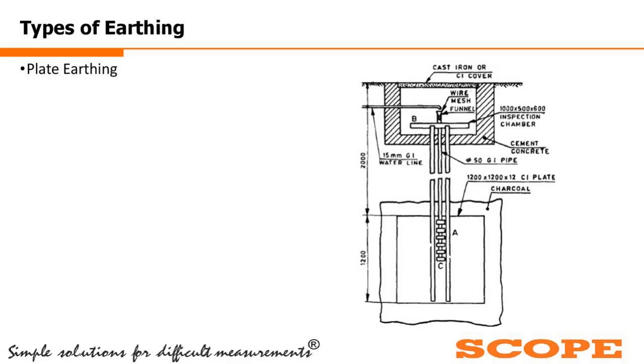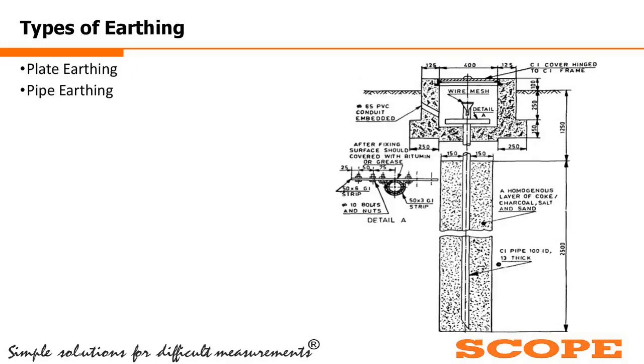Then comes the second way of earthing, pipe earthing. It is 90% or 99% similar to plate earthing, but the conductive plates are only replaced with a pipe. Earlier some people used hollow pipes, but nowadays people are using the solid rod, so it can be called rod earthing also.